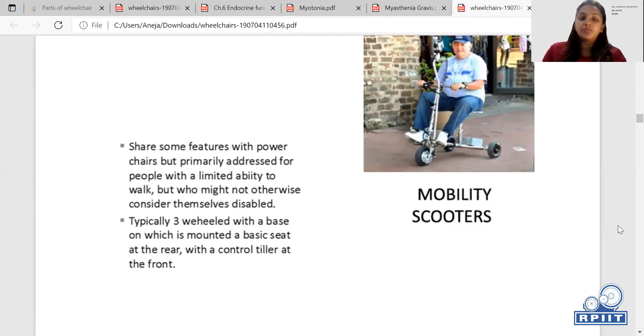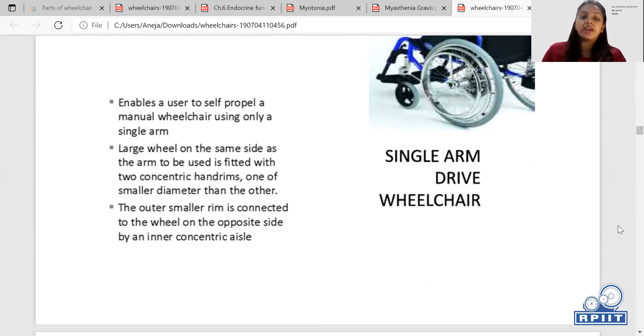Single arm drive chairs are for the hemiplegics. They enable the user to self-propel a manual wheelchair using only a single arm. The large wheel on the same side as the arm to be used is fitted with two concentric hand rims, one of a smaller diameter than the other. The outer smaller rim is connected to the wheel on the opposite side by an inner concentric axle.